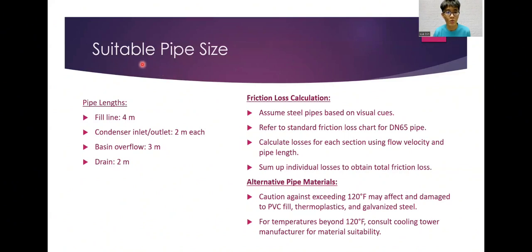Now I would like to present the suitable pipe size. The pipe size that we use is for pipe lengths of fill line 4 meters, condenser inlet and outlet 2 meters each, basin overflow 3 meters, drain 2 meters, and the friction loss calculation. We assume that it is a steel pipe based on visual cues, and we refer to a standard friction loss chart for DN 65 pipe, and we calculate the loss for each section using flow velocity and pipe length. Lastly, we sum all the individual losses to obtain the total friction loss.